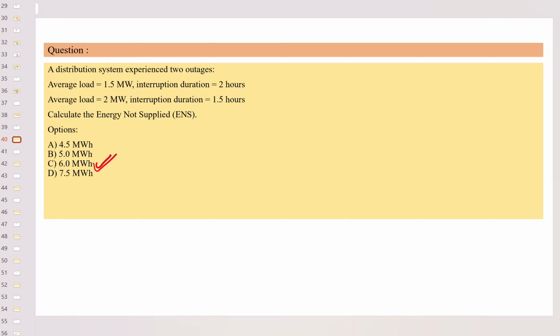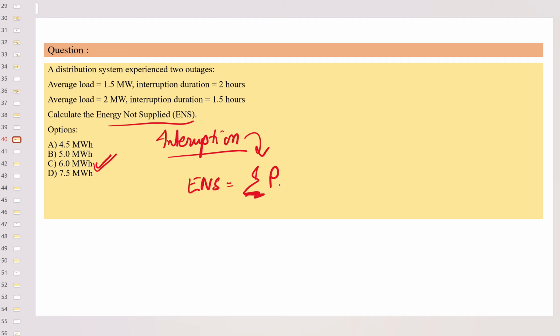That's true, and in this kind of problem that is very important: the key energy during the duration of interruption — how much energy was not supplied during that time. What you have to do is, ENS, energy not supplied, is simply equal to summation of power during the outage, Pi, during the interruption time, multiplied by the time of interruption.